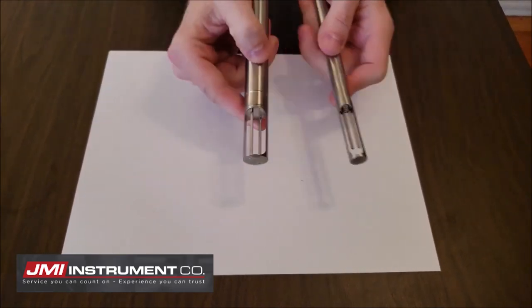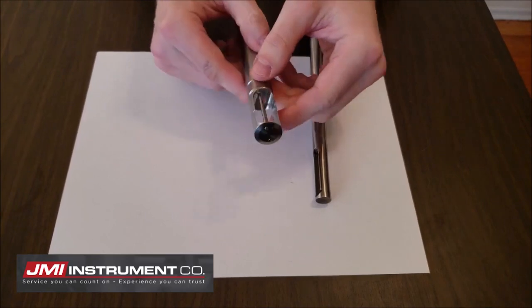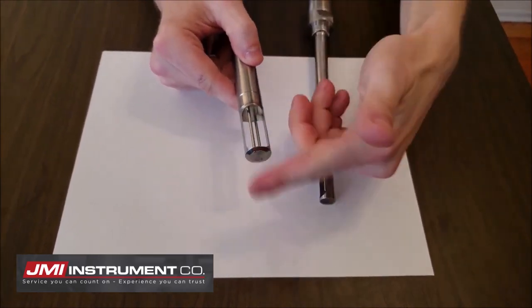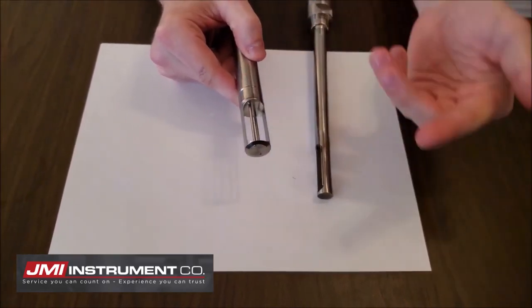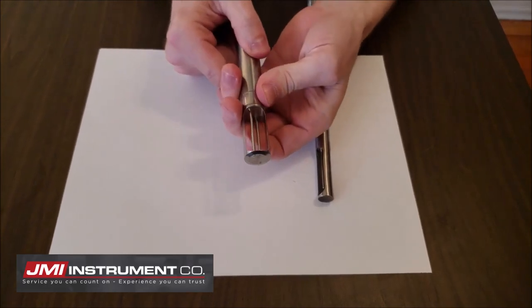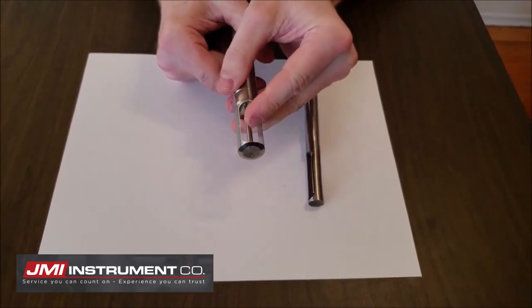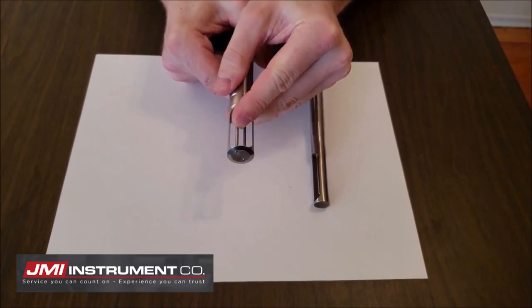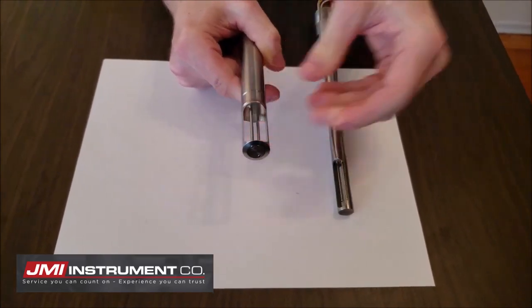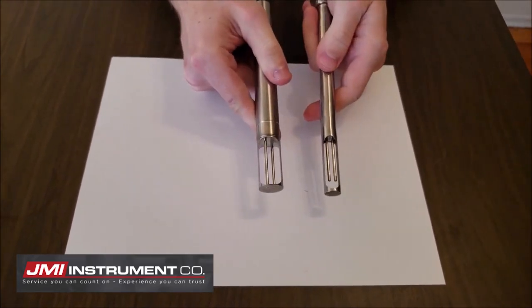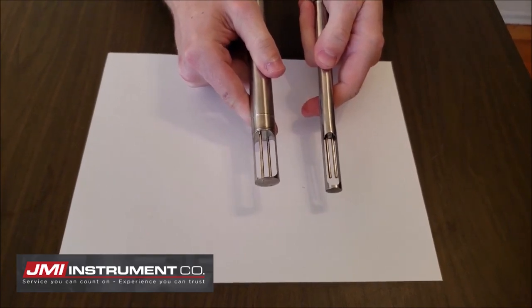Now, Fox Thermal offers non-cantilevered probes. Both sensors are welded on both ends. This allows for less vibration. You can see I can't even really move the probes with my fingers. They don't bend or waver in a wider range of process conditions. It's simple physics, but Fox Thermal did it right.